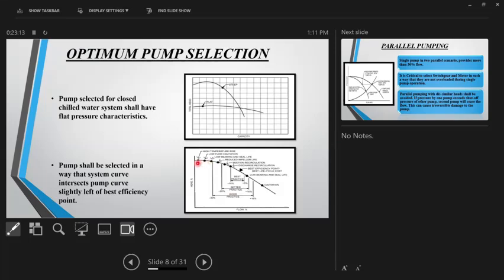Now, the extreme left-hand side is known as low cavitation, or low flow cavitation, where it is very clear that in these conditions the flows are less. So you could actually experience a very high temperature rise in the water. You could have cavitation, which may lead to bearing losses. So this obviously is to be avoided.